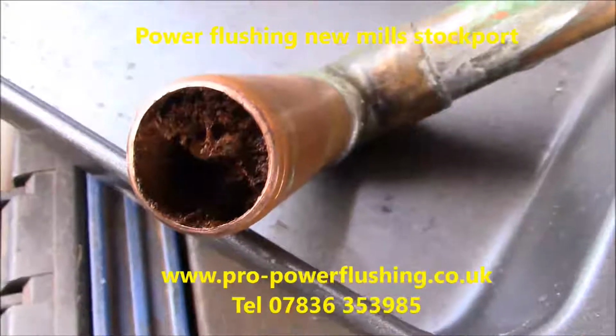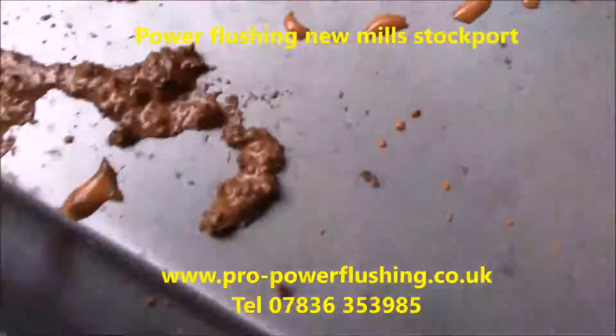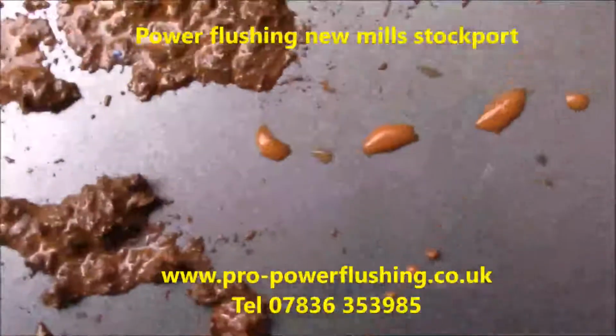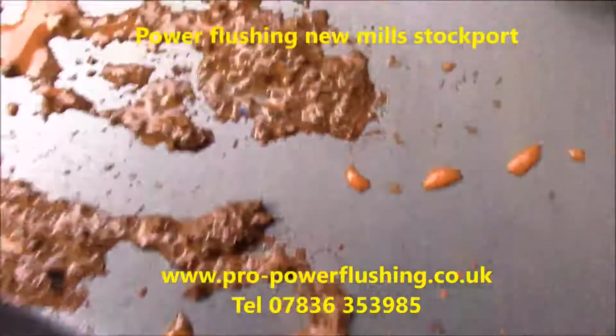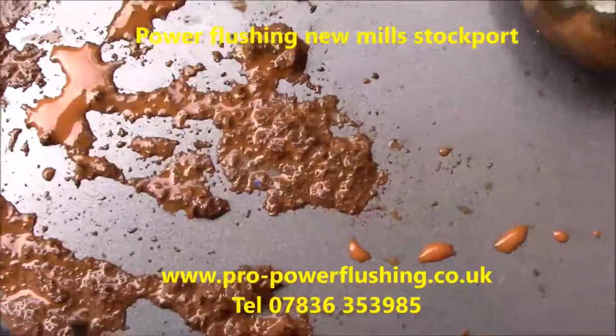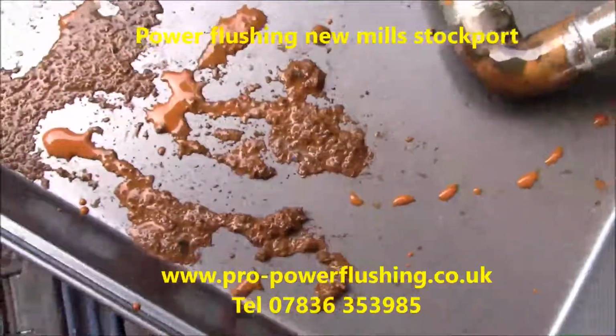So we're going to dig it out and we'll quickly get back to you, and then we'll get this power flush on again. So there's the rust, the corrosion and metal. Can you see that? Some has gone down the side there. That was in this central heating pump pipe. We're just going to show you that before we start the power flush. This is what power flushing is all about, getting all this rust, metal and corrosion out of the central heating system. Okay, thanks, get back to you.